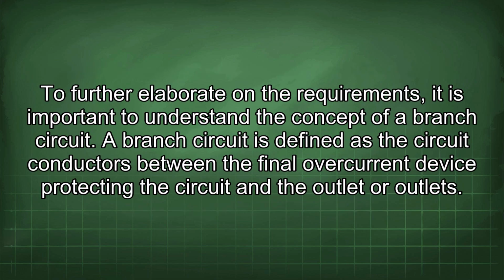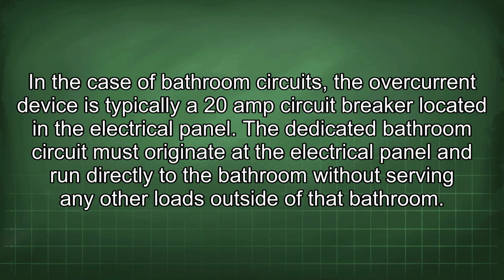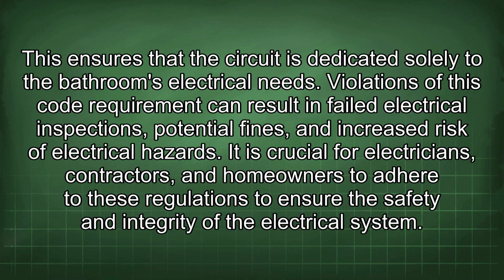To further elaborate on the requirements, it is important to understand the concept of a branch circuit. A branch circuit is defined as the circuit conductors between the final overcurrent device protecting the circuit and the outlet or outlets. In the case of bathroom circuits, the overcurrent device is typically a 20-amp circuit breaker located in the electrical panel. The dedicated bathroom circuit must originate at the electrical panel and run directly to the bathroom without serving any other loads outside of that bathroom. This ensures that the circuit is dedicated solely to the bathroom's electrical needs.